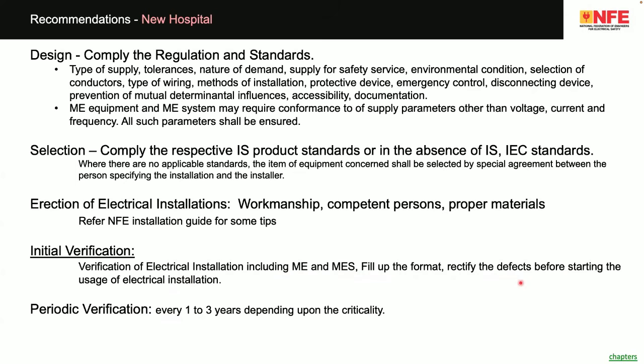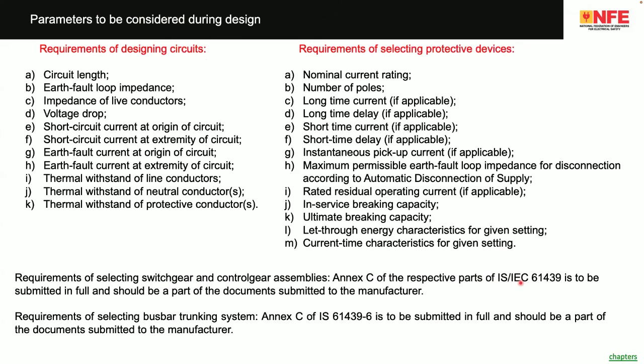The last one is periodic verification. Periodic verification, 1 to 3 years, you can make it. The list of examples of requirements, this is for the consultant. Normally, when consultants design electrical systems, they mostly only consider the voltage drop. Based on the voltage drop, the wires are selected. It is not only the voltage drop; there are multiple parameters which need to be considered while designing the electrical cables. Similarly, multiple parameters are to be considered when selecting a protective device. You must consider all these points in the design.